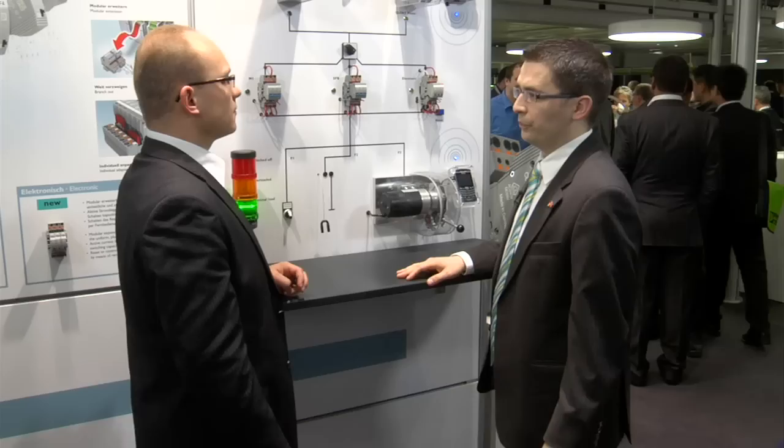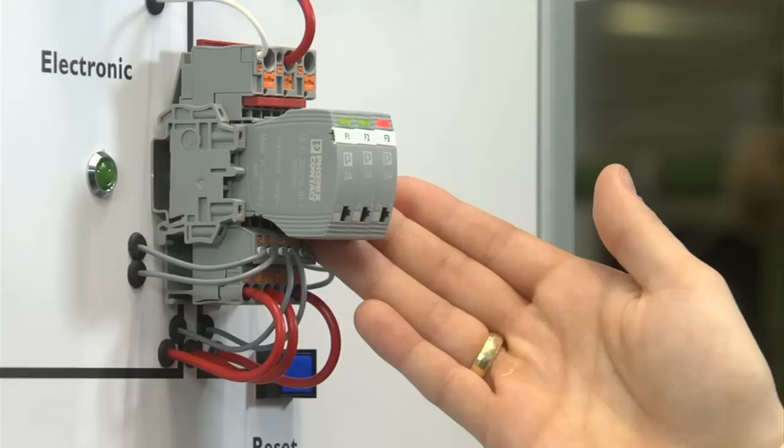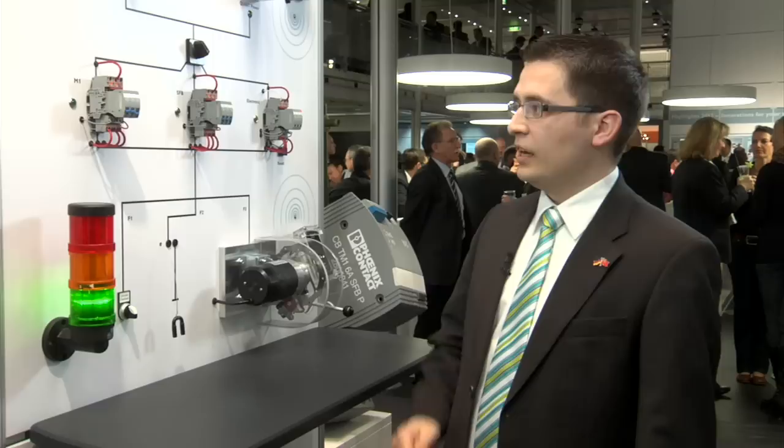New device circuit breakers from Phoenix Contact protect end devices reliably and simplify installation. On the one side, we have the new thermomagnetic device circuit breakers that have a special SFB characteristic curve for longer cable paths. And on the other side, we have new electronic device circuit breakers with active current limiting and a uniform remote signaling concept. All of this is located in a uniform plug-in housing concept that simplifies installation.